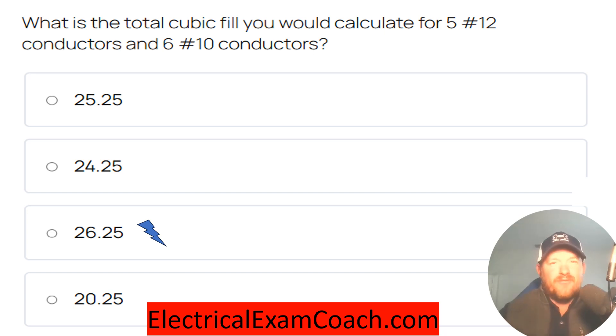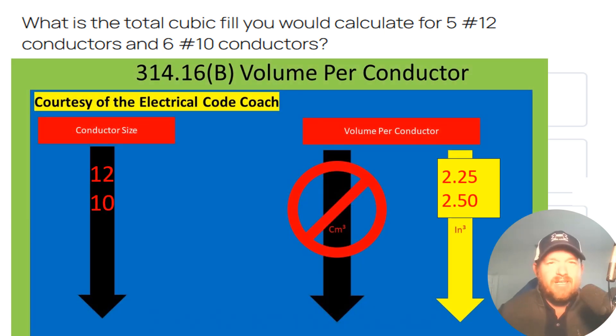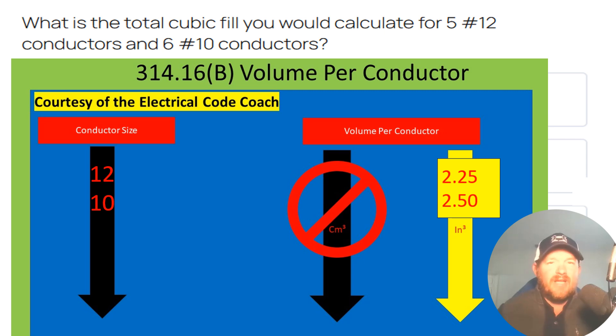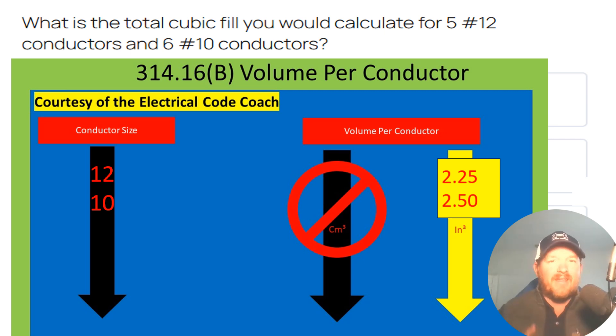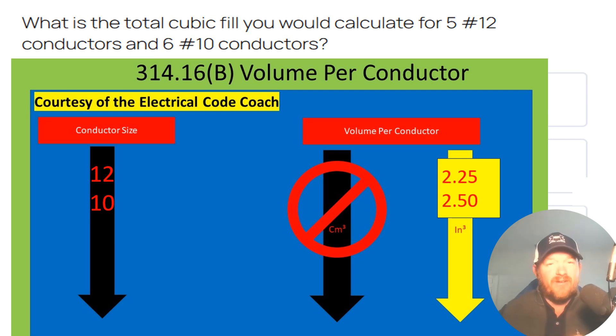For this one, we're going to head to NEC 314.16(b). We're going to start on our left-hand side and find our 12-gauge conductors, and we find that they are 2.25 cubic inches each. Then we find our 10s and find that they are 2.50 cubic inches each.